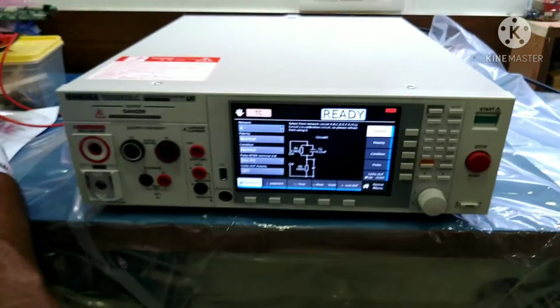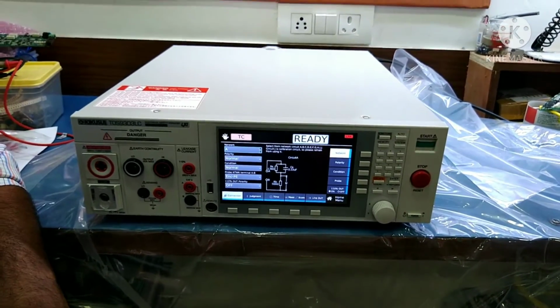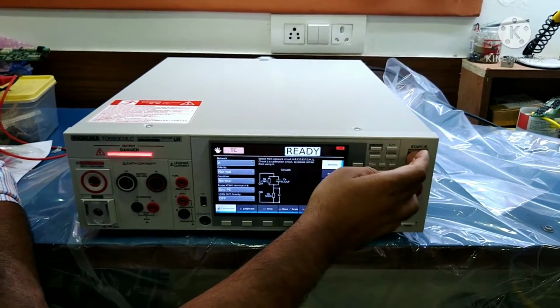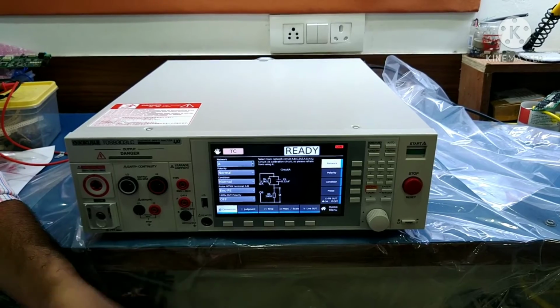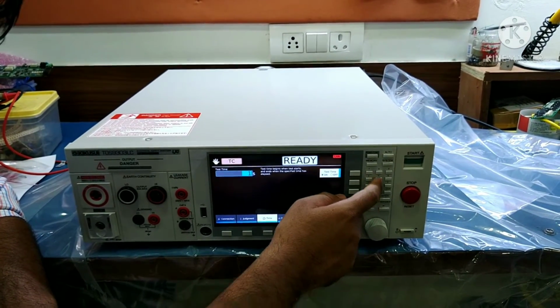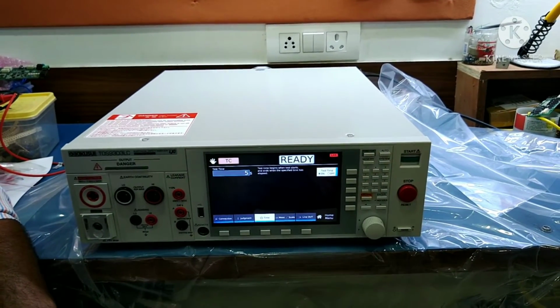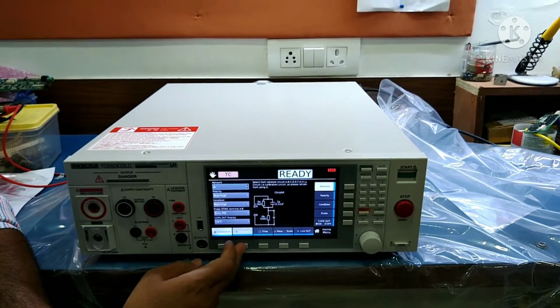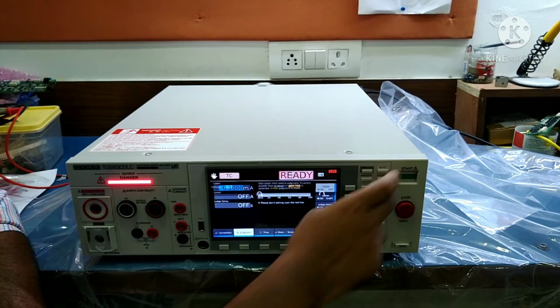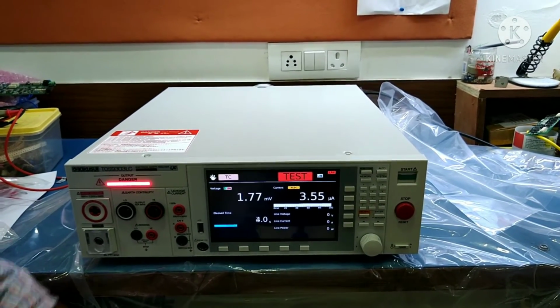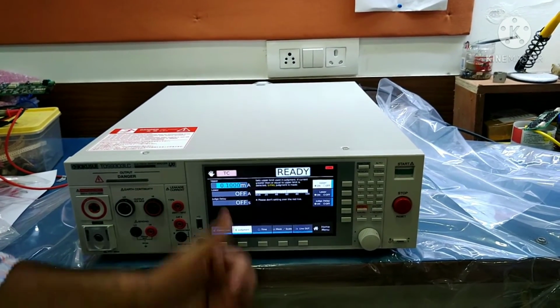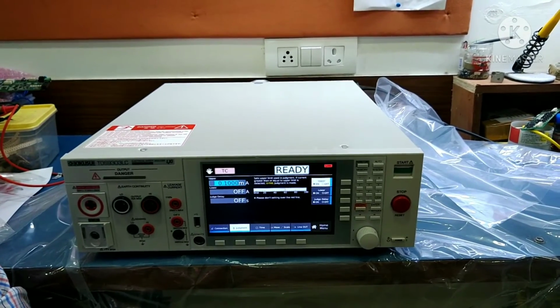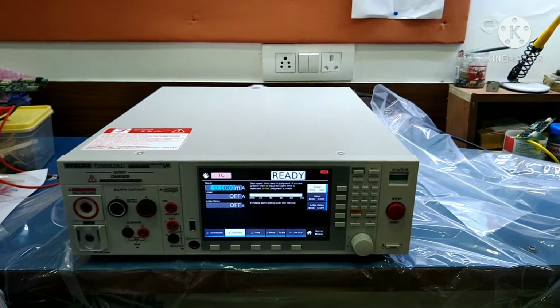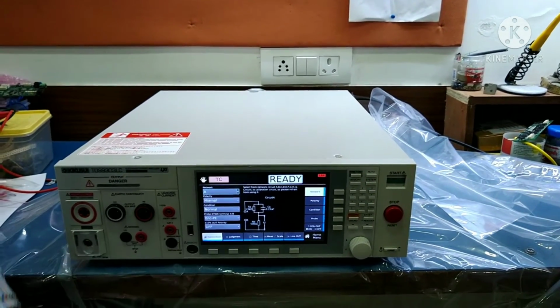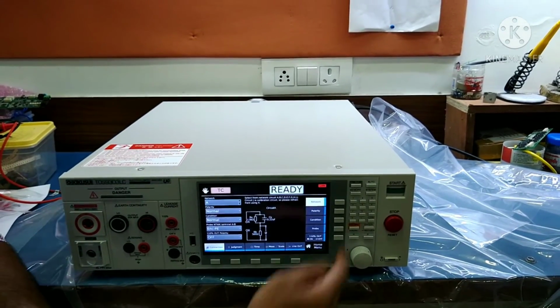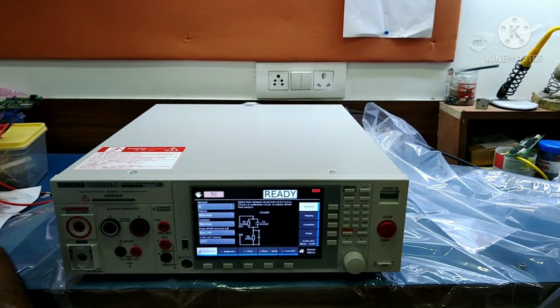In the open condition, by default it will obviously show pass because we are not making any circuitry. So we will test. Yeah, because it is for 1 second. This is only basic information on how to change the settings. This is an open condition. Because the limit value is very low, it will show pass. Once we connect it, it will show the required current between this probe position, that is the enclosure and the protective earth.